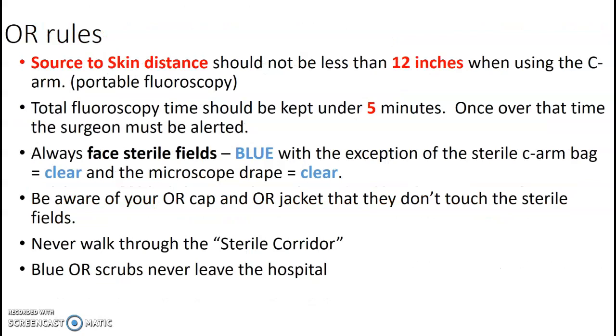Some OR rules. Source to skin distance for when using the C-arm, which is considered portable fluoroscopy, shouldn't be less than 12 inches. So be aware of where your source is and where the patient's skin is. Just like fluoro, the fluoro time should be kept under 5 minutes, and it will have that alert bell, right? It has to have that audible noise per the FDA, just like your fluoro machines do. And it'll look like that little bell icon, similar to that of their fluoro table.